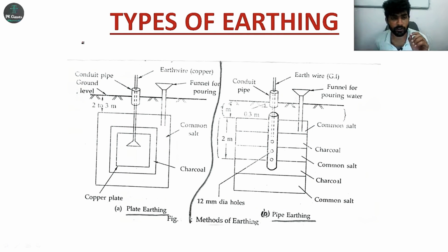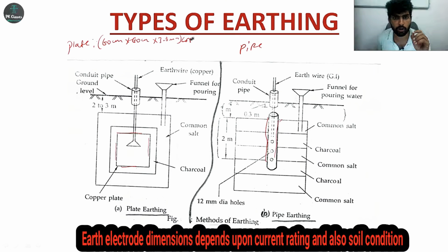Based on the earth electrode, we differentiate one as plate earthing, another as pipe earthing, right? One looks like a pipe, and this one is a plate, right? The dimensions are 60 centimeters by 60 centimeters, with 3.8 millimeters thickness for a copper electrode, and similarly 60 by 60, length and width, with 6.5 millimeters thickness for galvanized iron.